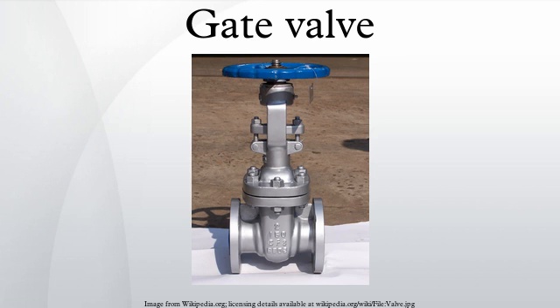A partially open gate disc tends to vibrate from the fluid flow. Most of the flow change occurs near shut-off, with a relatively high fluid velocity causing disc and seat wear and eventual leakage if used to regulate flow.